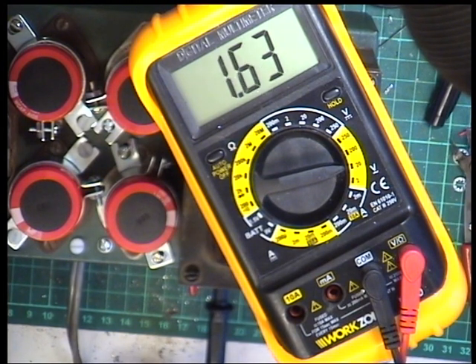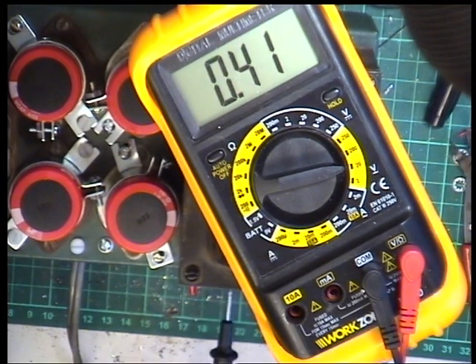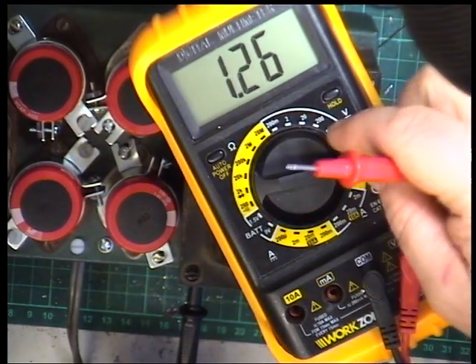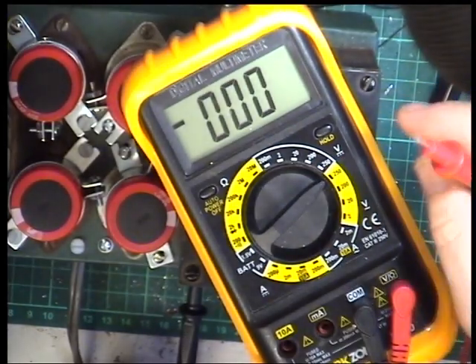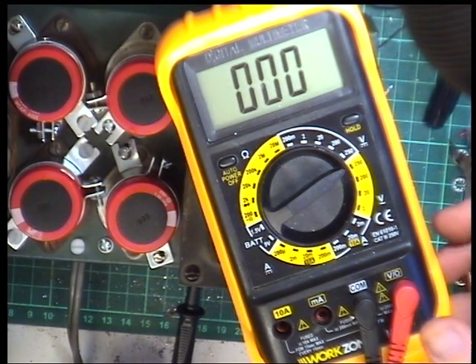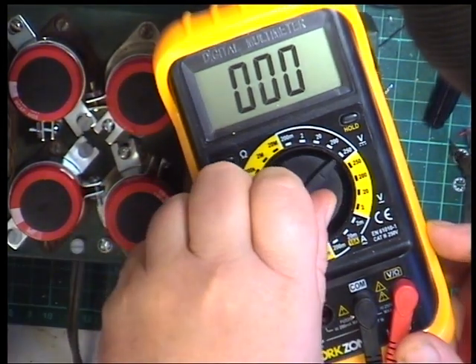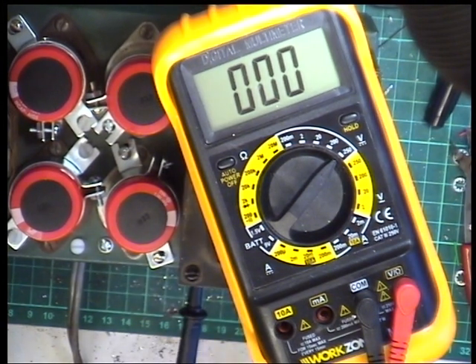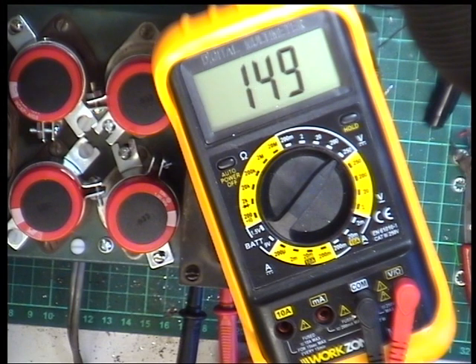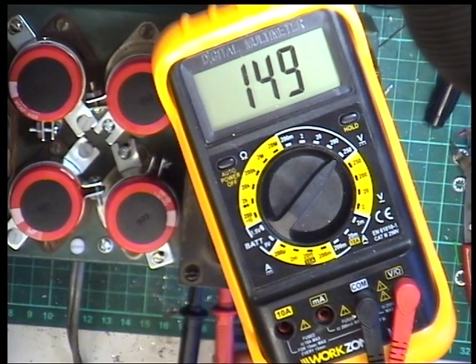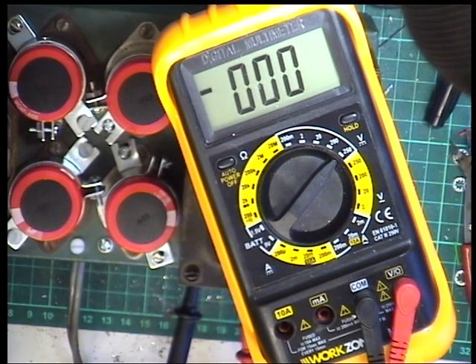So if we go to ground and switch to... oh, this meter doesn't go up there. Well, because we're running at half voltage on 115, chances are the 250 volt line won't be exactly half because it's off load, but it should be within the meter's capability. So we'll go into there... 149. But half of the 850 volt line would still be too much for the meter. Now we'll look at the bias, minus 130 it should be, so it should be half that, minus 70. So it looks like it is a 230 volt model.